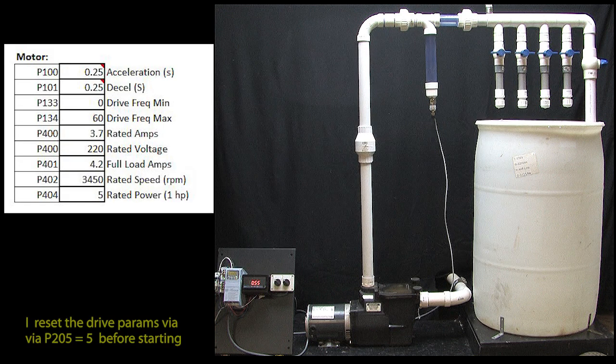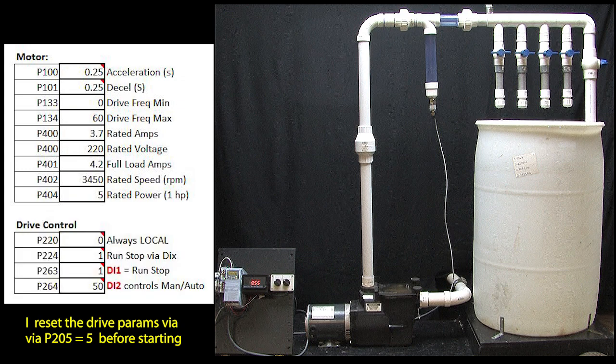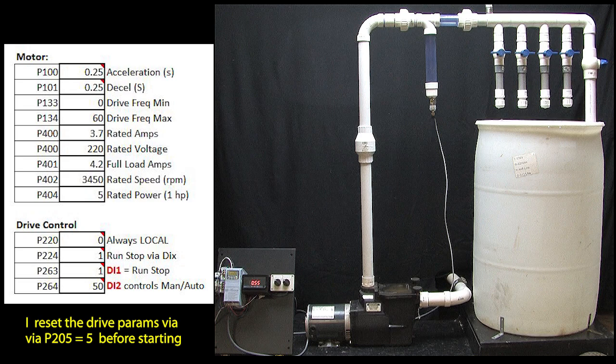I have already entered these basic parameters for the motor and these for the drive control which says we are only using local mode and it assigns the digital inputs. We are not actually using analog input 1 yet, but it does default to 0 to 10 volts so we don't need to change that.